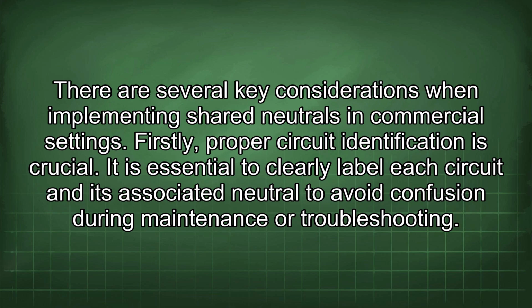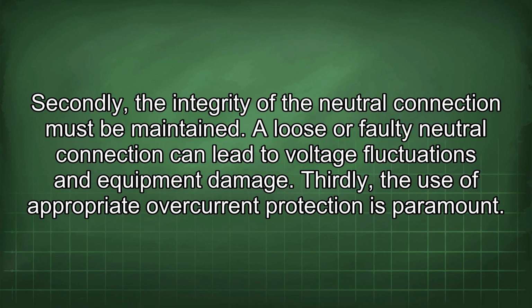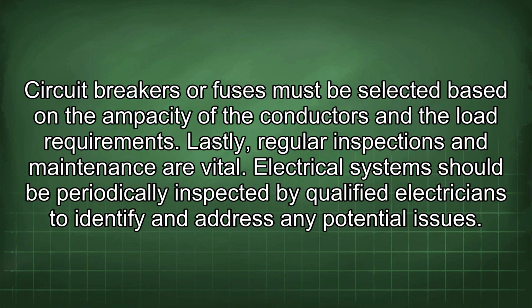There are several key considerations when implementing shared neutrals in commercial settings. Firstly, proper circuit identification is crucial. It is essential to clearly label each circuit and its associated neutral to avoid confusion during maintenance or troubleshooting. Secondly, the integrity of the neutral connection must be maintained. A loose or faulty neutral connection can lead to voltage fluctuations and equipment damage. Thirdly, the use of appropriate overcurrent protection is paramount. Circuit breakers or fuses must be selected based on the ampacity of the conductors and the load requirements. Lastly, regular inspections and maintenance are vital. Electrical systems should be periodically inspected by qualified electricians to identify and address any potential issues.